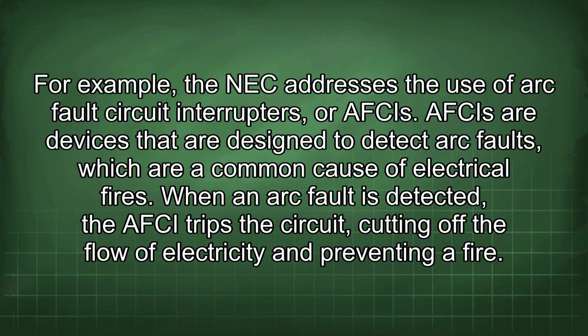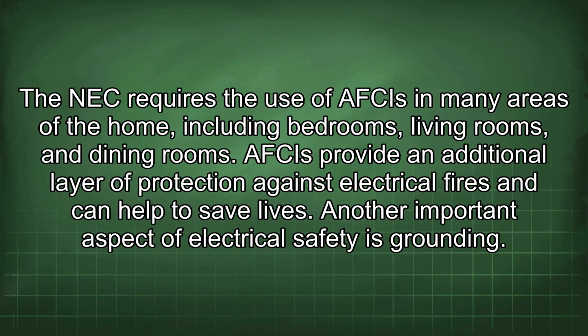For example, the NEC addresses the use of arc fault circuit interrupters, or AFCIs. AFCIs are devices that are designed to detect arc faults, which are a common cause of electrical fires. When an arc fault is detected, the AFCI trips the circuit, cutting off the flow of electricity and preventing a fire. The NEC requires the use of AFCIs in many areas of the home, including bedrooms, living rooms, and dining rooms. AFCIs provide an additional layer of protection against electrical fires and can help to save lives.